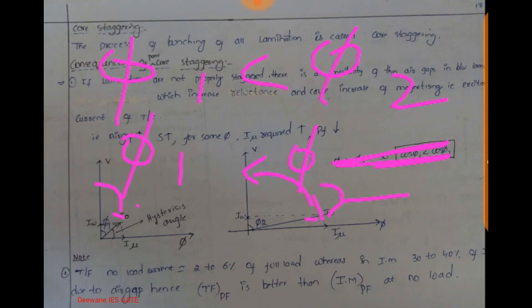One more point: the no-load current of a transformer is 2 to 6 percent of full load, whereas in an induction machine it is 30 to 40 percent because of the air gap. This is the reason why in all rotating machines — whether DC or AC — we are not using CR-GO steel; we are settling for silicon steel. Because even if you use CR-GO steel, you cannot reduce the air gap, so imu is still very high. Also, the cost of CR-GO is very high and it must be imported because that technology is not available in India.